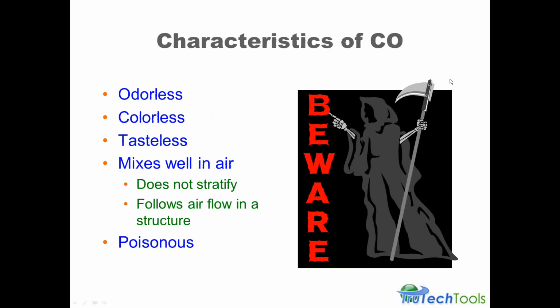So what are the chemical or physical characteristics of carbon monoxide? It's something to be aware of. It's odorless. You can't smell it. Colorless. You can't see it. Tasteless. It doesn't taste like some gases do. It mixes well in the air. It's about the same density as air molecules, so it doesn't stratify. It doesn't pool near the ceiling or near the floor. It does follow, therefore, the airflow in a structure, so it'll get around in distribution air and ventilation air, whatever is happening inside the structure. The carbon monoxide is just going to go on its merry way along with the air. So that's a deadly combination on top of the fact that it's poisonous to people and animals. Those physical characteristics make it very hard to detect without using some kind of sensor.